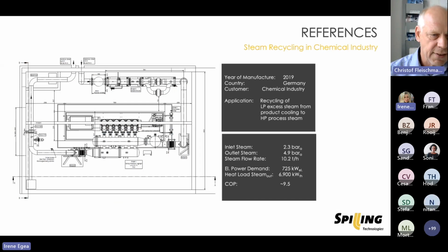Here is also a 6-cylinder compressor, shown as an installation drawing. It's installed at a chemical plant in Germany where steam is recycled. The steam on the source side is coming from a product cooling. It's available at 2.3 bar absolute. And the demand on this side is at a higher pressure level of 4.9 bar absolute. They have a steam distributing pipe which is supplying heat for different consumers.